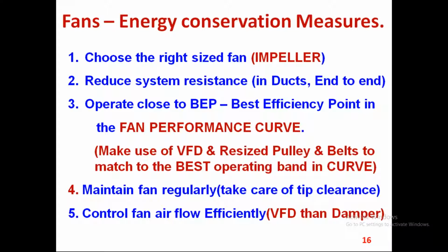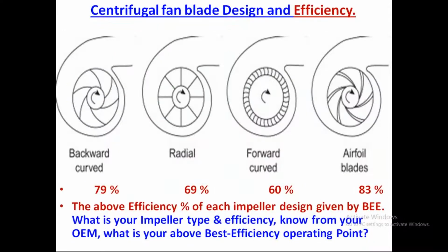So maintain the fan regularly and maintain the tip clearance. This tip clearance is a critical area where the vena contracta point, if it is given more, then the loss is between 10 to 20% also. So instead of a damper effect, damper is the least efficient, whereas a VFD is the most efficient. Coming to the impellers, this backward curved impeller is almost 79%, whereas a radial impeller is at 69%. Many of the exhaust fans are using this radial type.